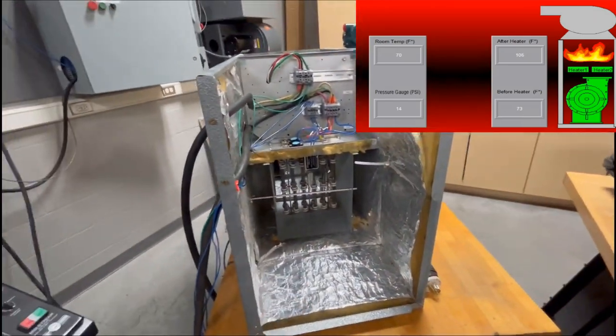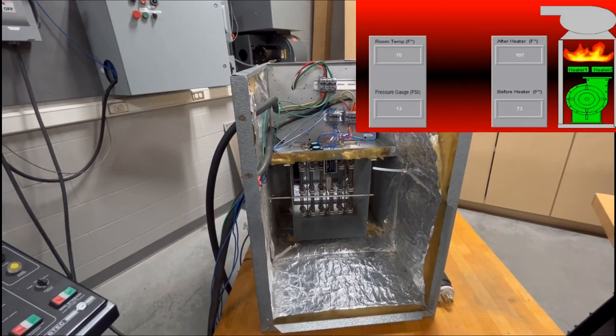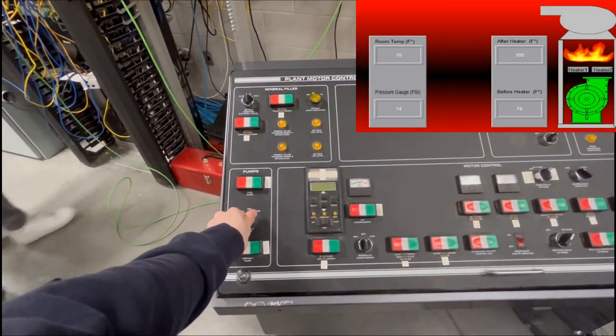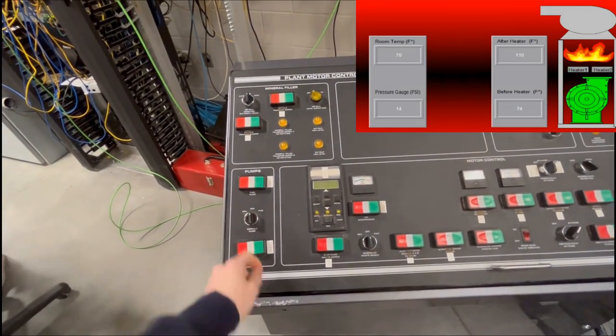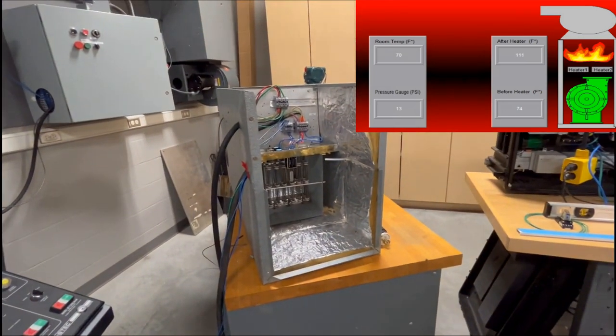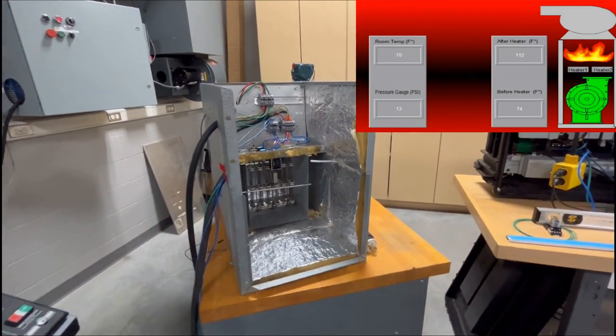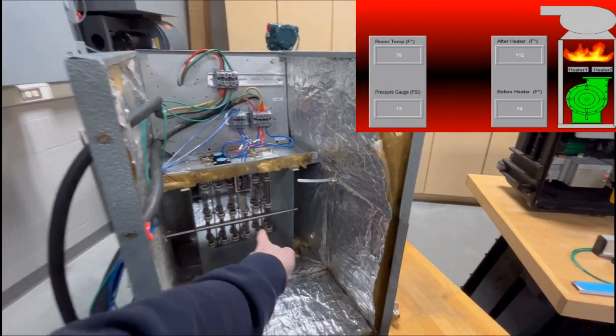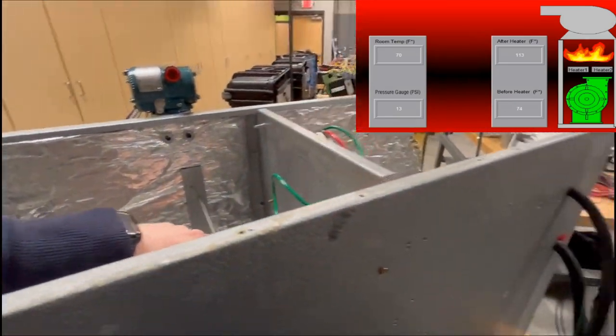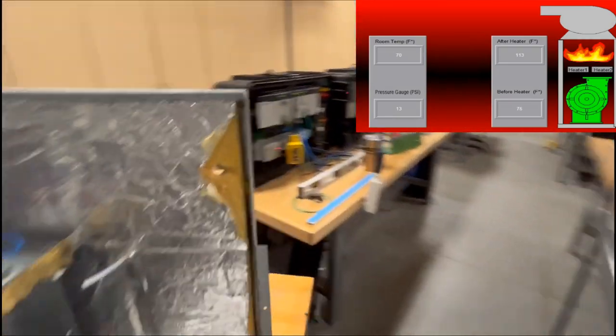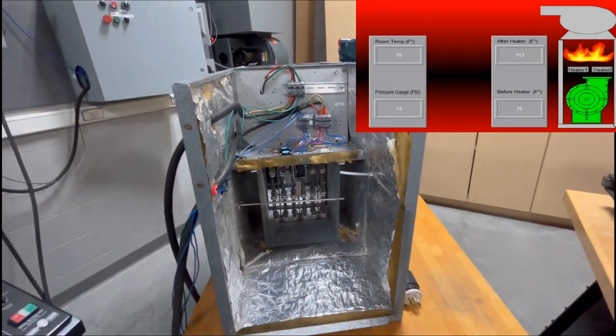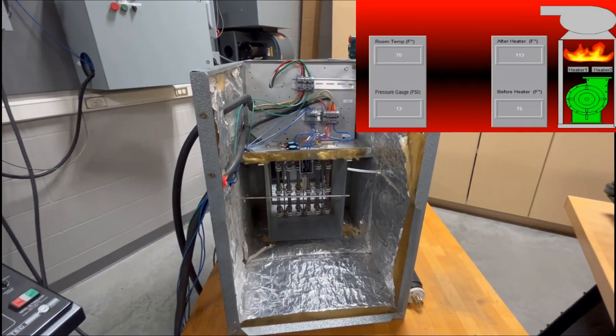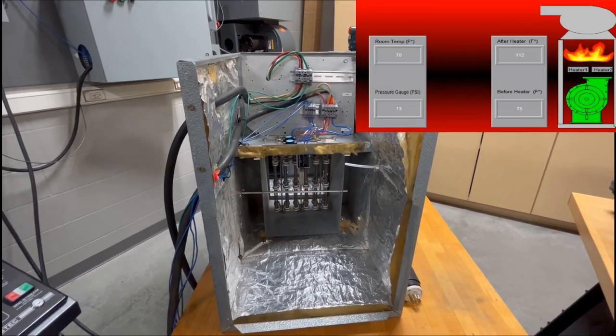Pretty simple device. You could use it to heat up a shop or anything in a classroom. And then we can turn off the heaters by just turning the selector switch to off. And this blower is going to run until this temp probe is within 5 degrees of this temp probe, because we don't want to have all the heat in those coils. We want to get all that heat out so we don't melt something or cause a fire.